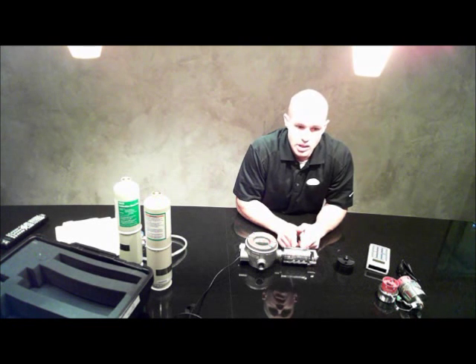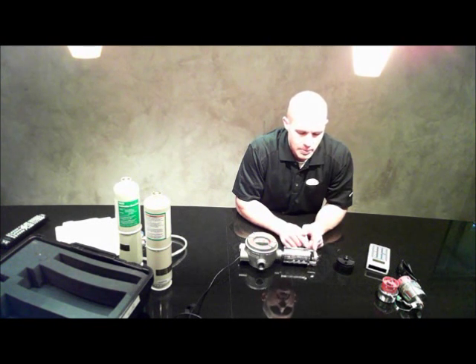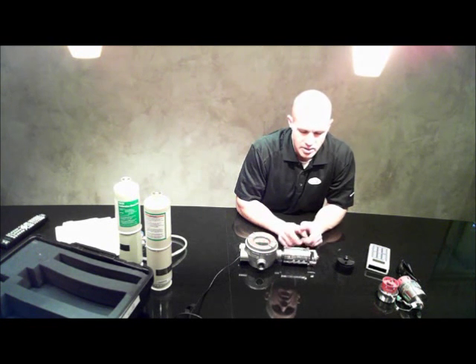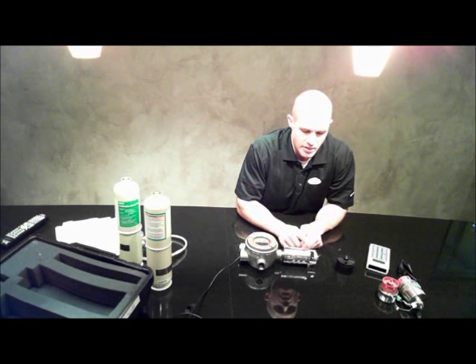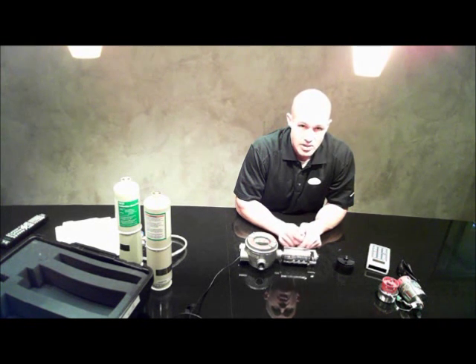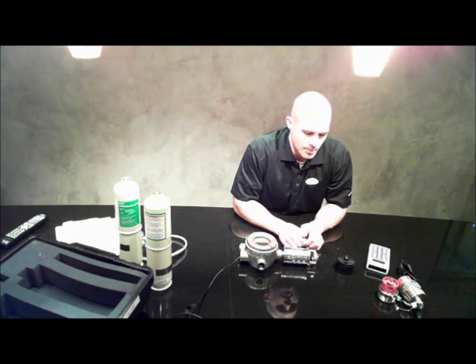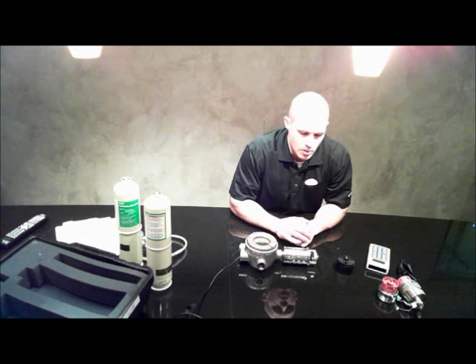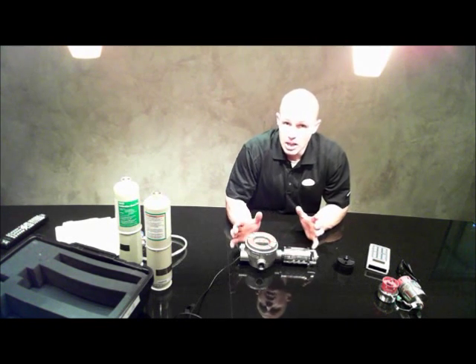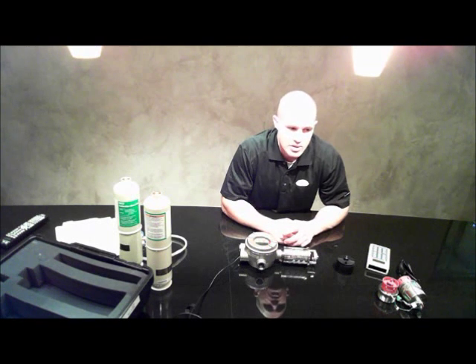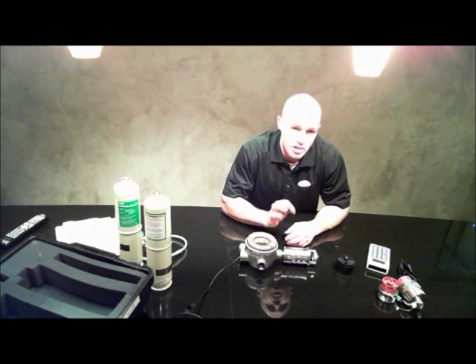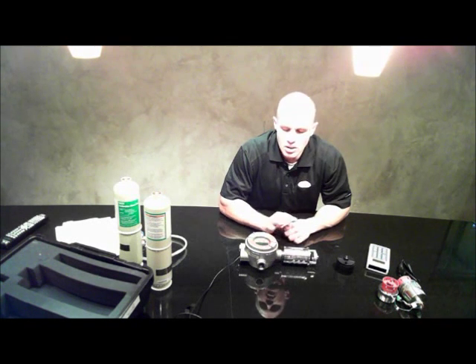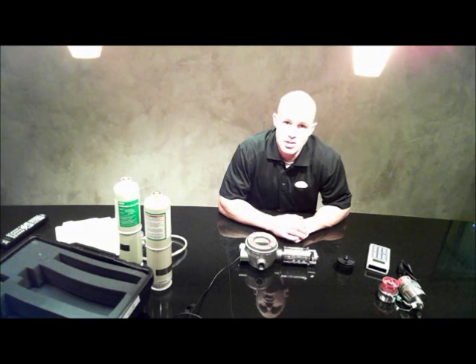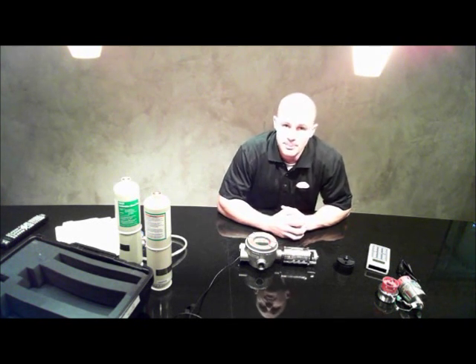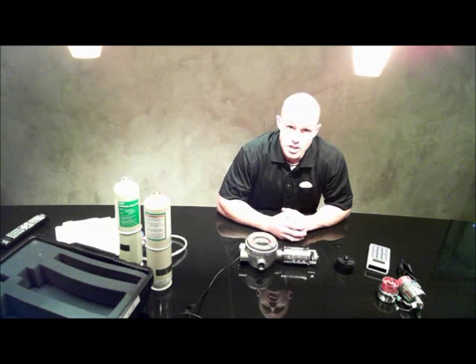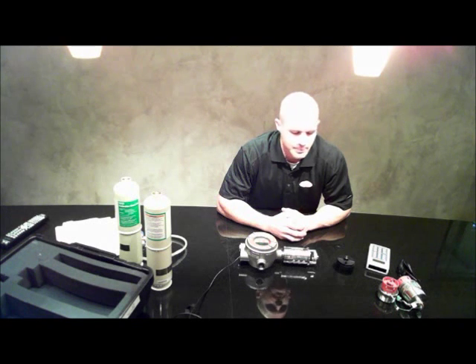There's an infrared light source that's generated in here. There's a sapphire mirror here, or a mirror here, and I guess it's a sapphire lens in there. Infrared's shot out, bounced off the mirror, and read back inside the housing here. So if you're getting low signal messages on here, or things just don't seem to be jiving and calibrations aren't fixing things, it's a good idea to check that lens. You can use isopropyl alcohol and a Q-tip to clean that lens off, and that should be good. There's a cleaning mode function that you want to put this in. Otherwise, with isopropyl alcohol, you run the risk of setting off alarms depending on the style of sensor that you're using. So you do want to be careful with that.